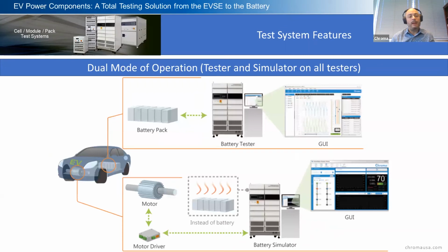We have a dual mode of operation, which in reality could be 4 different modes. We could be a tester, testing the actual EV battery through a charge and discharge profile, running a DCIR test, capacity test, etc. Or we can simulate the actual battery pack - it's the same equipment, just a different software platform, whether you're running your recipe or doing an actual battery simulation. So it helps with both battery development and battery testing.